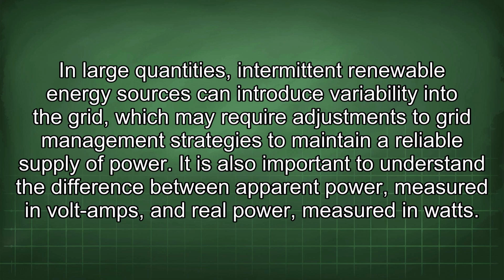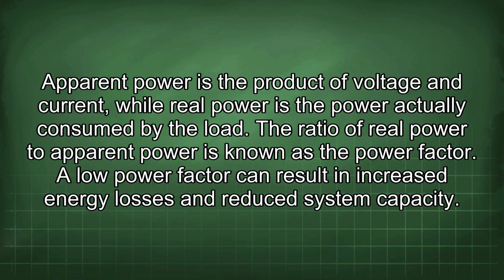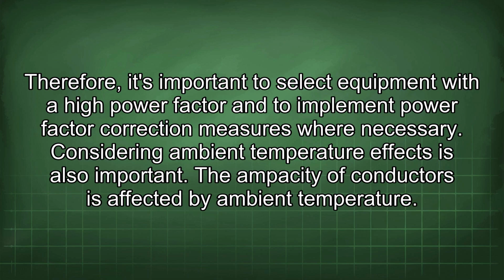It is also important to understand the difference between apparent power, measured in voltamps, and real power, measured in watts. Apparent power is the product of voltage and current, while real power is the power actually consumed by the load. The ratio of real power to apparent power is known as the power factor. A low power factor can result in increased energy losses and reduced system capacity. Therefore, it's important to select equipment with a high power factor and to implement power factor correction measures when necessary.